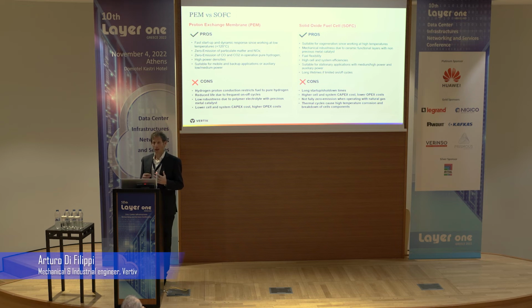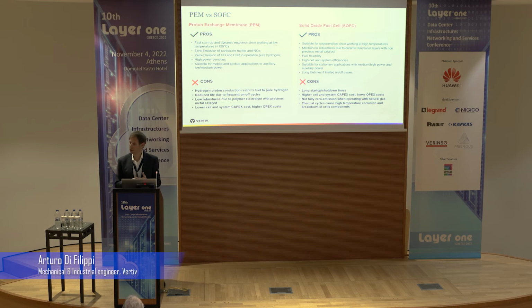The pros of the PEM fuel cell are that they are emission free, which is why they will be adopted by these hyperscalers. They work at low temperature, so they are quick. You can use them for backup power applications, replacing diesel generators, because they take seconds to switch on and off, and they can cycle frequently in a short time.